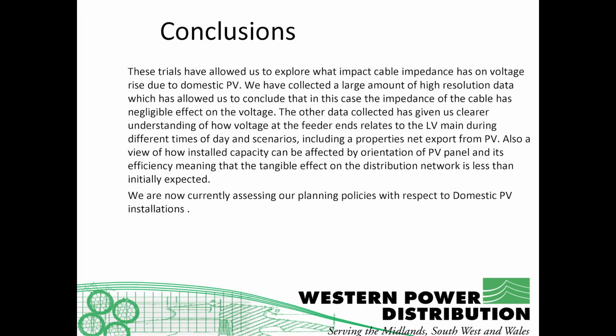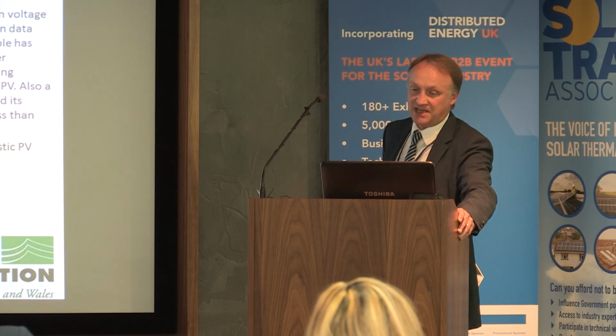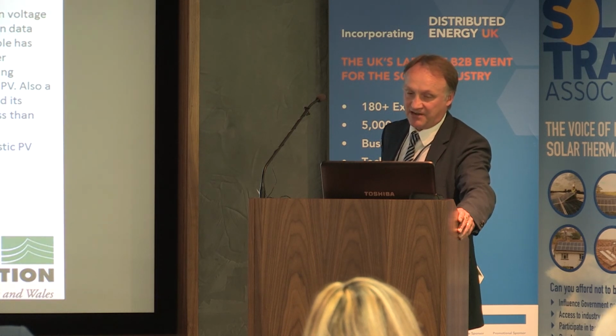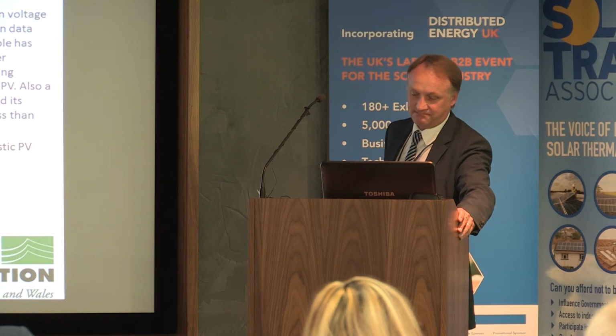So finally, just as a conclusion, these trials have allowed us to explore what impact cable impedance has on voltage rise due to domestic PV. We've collected a large amount of high-resolution data, which has allowed us to conclude that in this case the impedance of the cables has negligible effect on the voltage. The other data collected has given us a clearer understanding of how voltage at feeder ends relates to the LV main during different times of day and scenarios, including a property's net export of PV. Also, a view of how installed capacity can be affected by the orientation of a PV panel and its efficiency, meaning that the tangible effect on the distribution network is less than initially expected. We're now currently assessing our planning policies with respect to domestic PV installations. And that's it.